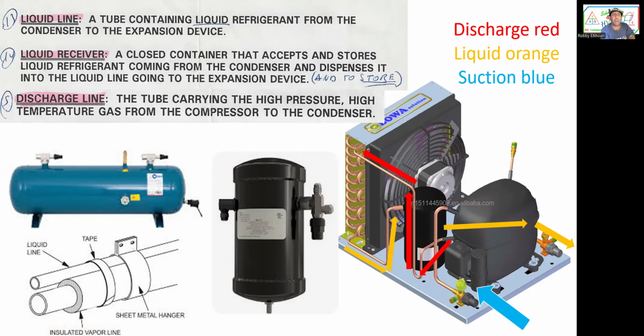It will make damage if it's a cap tube system. Liquid receiver is a very important part of refrigeration and air conditioning. Small systems don't have it. It's not needed. Big system is needed for sure. Also, if you have a leak, you don't have to recover all the refrigerant. It's also a storage device. You can pump down, pump all the refrigerant into the receiver and save it there, do whatever you want to do in the system, and then open it up.